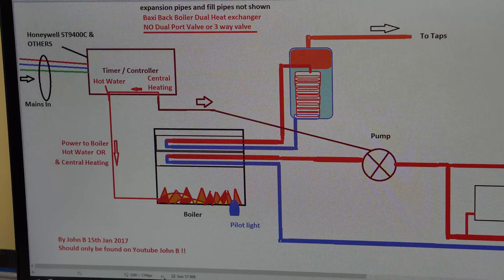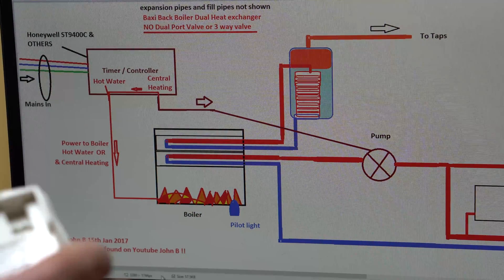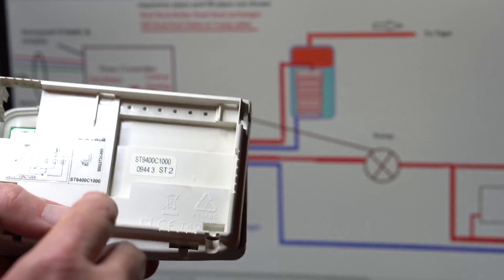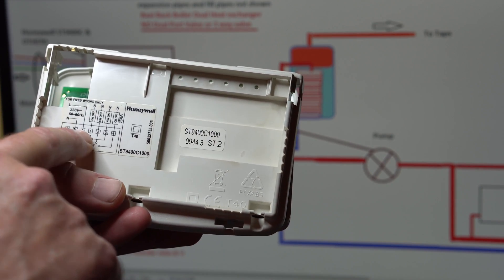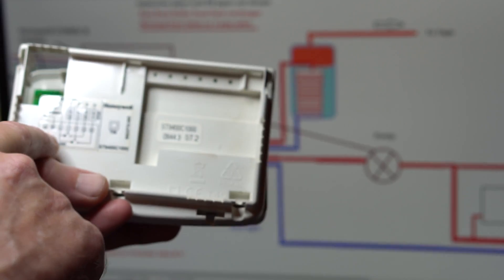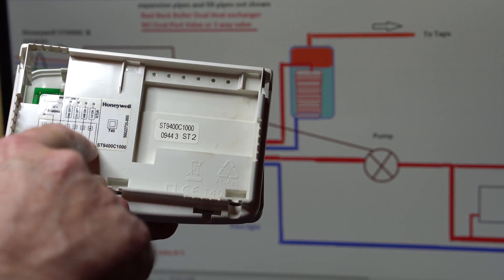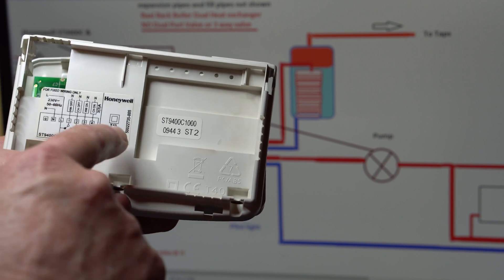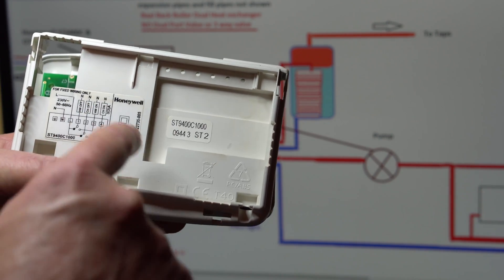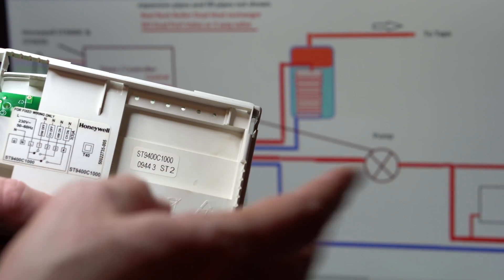And if you're stuck, you're in the middle of nowhere and it's midnight or whatever, there's a quick look at the drawing. You've got live neutral in plus an earth. These pins, there's no earth on the pins. Just shows you this was a simple one. Live out to the boiler, live out to the pump. In this case, what I did, bridged the two wires going out to the pump and to the boiler, bridged them straight to live. So if she wants to turn it off, pulls the fuse until I fix this.